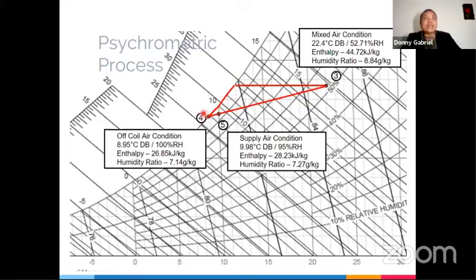However, the coil manufacturer gives you what they call a bypass factor. So what is a bypass factor? Bypass factor is the amount of air that is bypassing your cooling coil. Your cooling coil, if you say 24,000 cubic meters per hour is passing through your coil, not all 24,000 are being cooled down. Some of them are just passing through. There's no change in them. So your coil manufacturer will give you a number called the bypass factor.